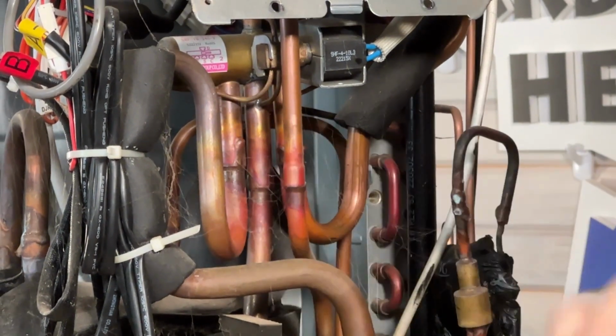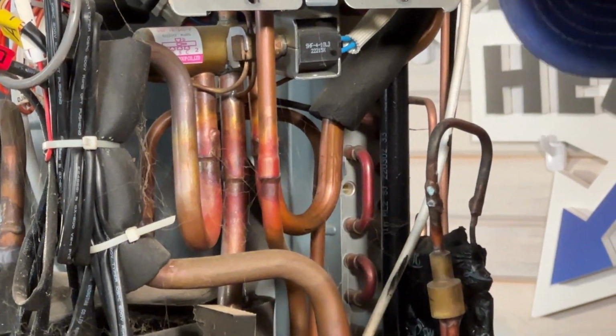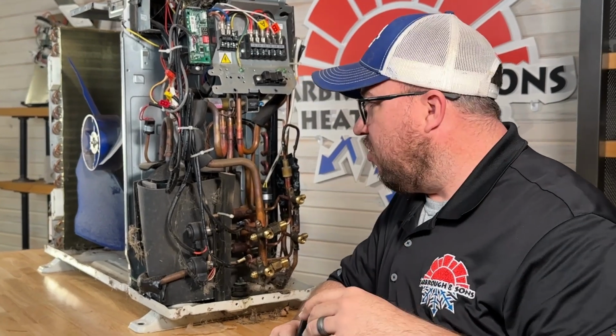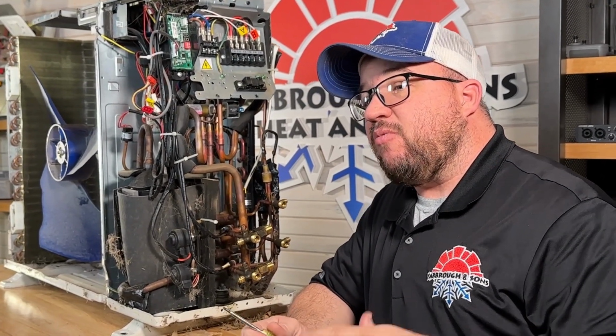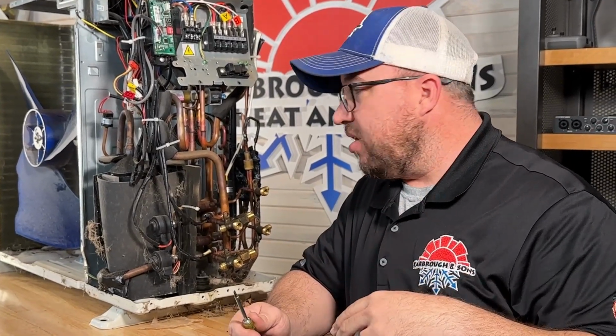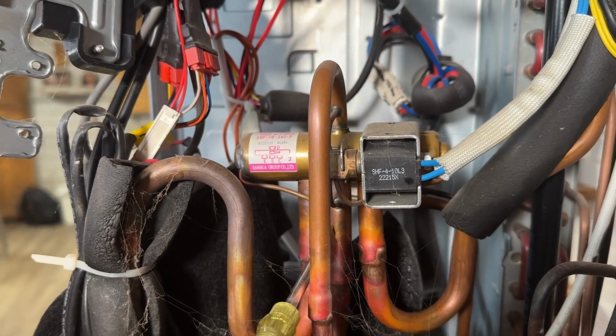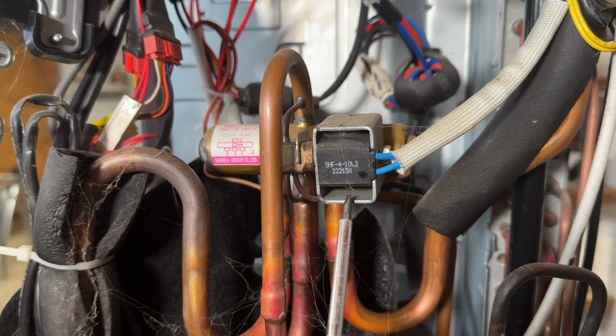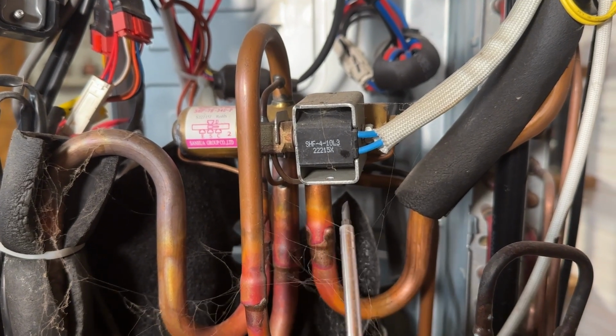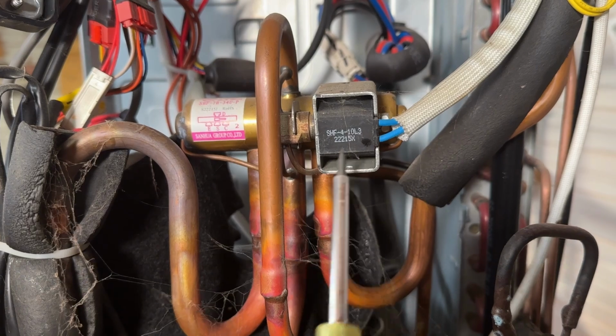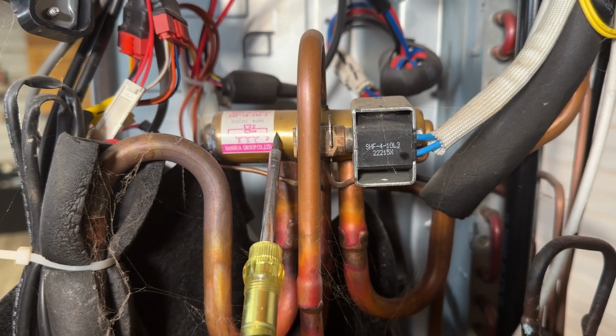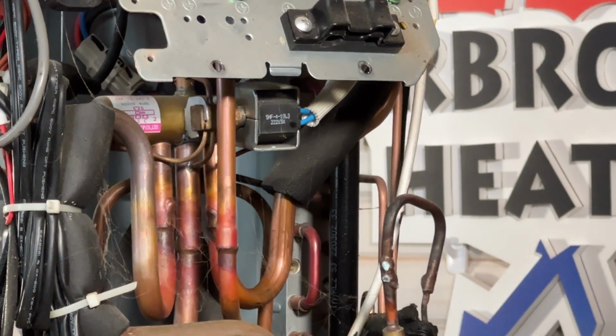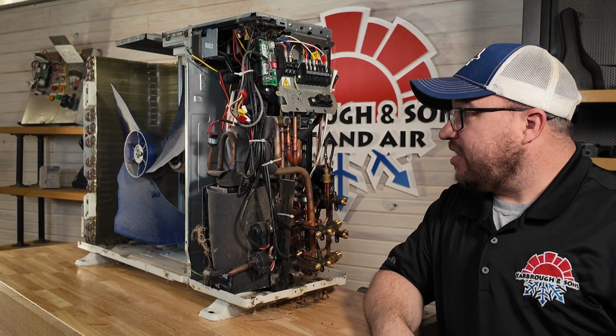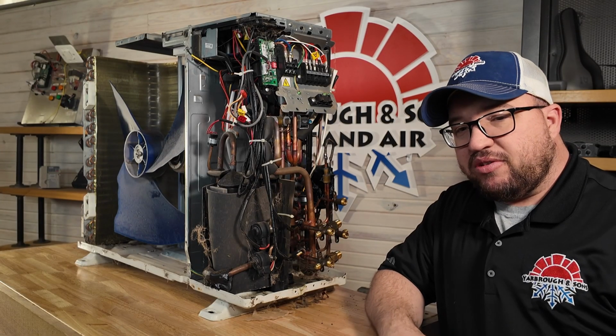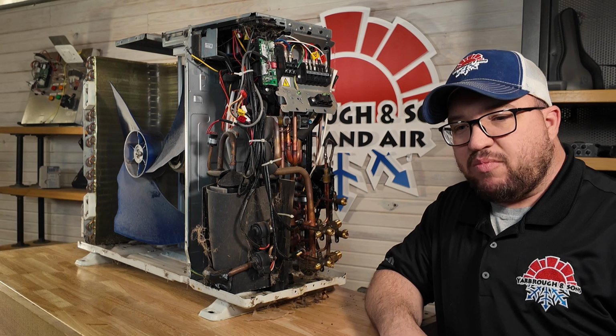This reversing valve is actually what makes this a heat pump. In a normal AC unit, you won't have a reversing valve. All that reversing valve is, is an actual device that will reverse the flow of refrigerant. Pretty neat little device, it just uses a solenoid. Typically on these it's 240 volt or 110, depending on what the power of the system is. On most heat pumps for your standard units it's 24 volts, but they all work the same way. Pretty great little device, it makes it where it's able to do heat, and that's a big improvement.